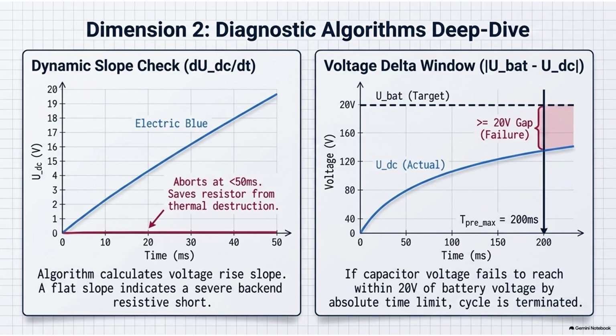That is the exact logic, and it serves a critical protective function. By aborting early based on the slope, the system prevents the pre-charge resistor from having to absorb the remaining duration of short-circuit current. It effectively saves the component from melting down. That is incredibly smart. But let's say the slope looks good, the voltage is rising, the pool is filling. The system still has a hard deadline, right? Yes. Depending on the battery chemistry and capacitance, the system defines a maximum allowable pre-charge time, frequently around 200 milliseconds.